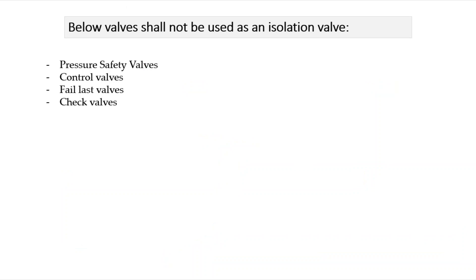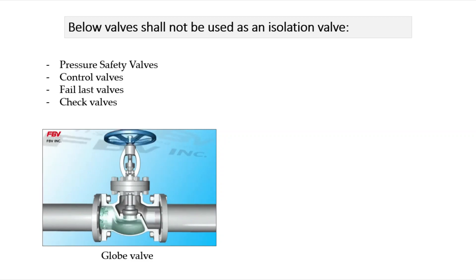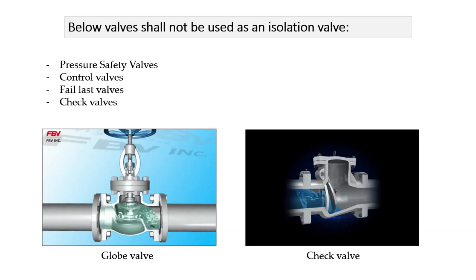It should also be noted that not all valves are suitable for use in an isolation process because of their design. For example, a risk of malfunction or accidental opening as a result of pressure changes makes control valves such as a globe valve unreliable for such a critical duty. The same thing applies to a check valve, with the addition of a physical impossibility to implement isolation with it.